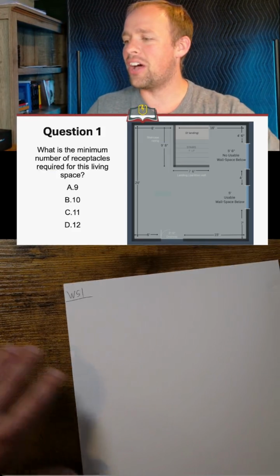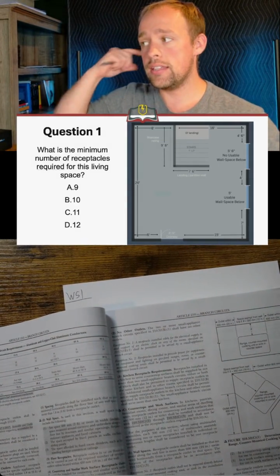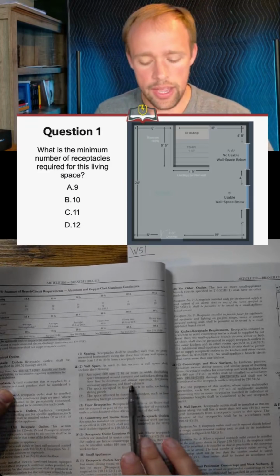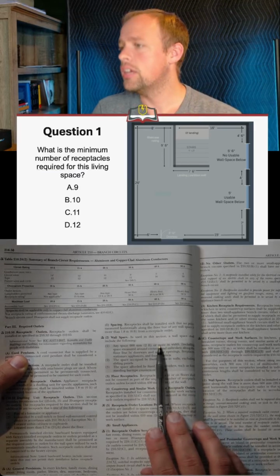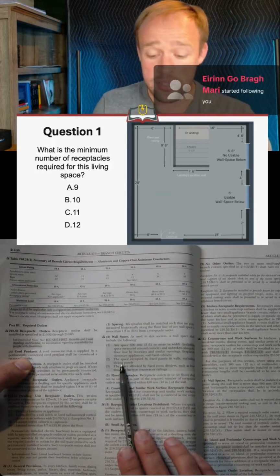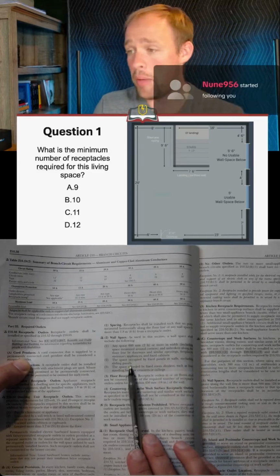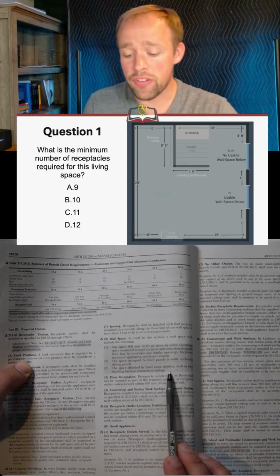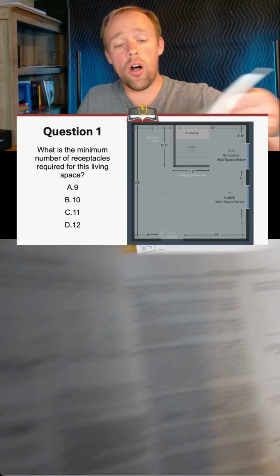So you should be asking yourself, okay, Richie's saying the landings, so is a railing a wall space? Let's go here. Again, this is under the definition of a wall space. There you go, Richie, I see what you mean now. So 1 was the definition of a wall space, 2 feet or more in width, including spaces around corners. 2 says a wall space is also the space occupied by fixed panels and walls, excluding sliding panels. So that's not part of this question. 3 says the space afforded by fixed room dividers, such as freestanding bar-type counters or railings. So railings are a wall space as well.